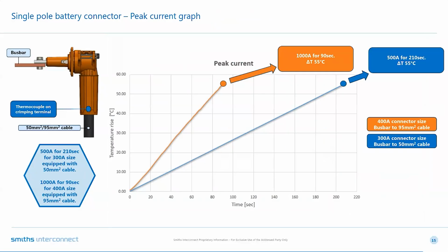The last test we are going to present is the peak current one that we mentioned before. The setup is the same as before, but providing the connector with a current value greater than the nominal one. This test simulates a typical operating situation when there is a demand for extra current just for a limited amount of time without exceeding in the connector overheating. Analyzing the chart, the x-axis shows the time in seconds, and the y-axis shows the temperature difference between the connector and the ambient. The test stops when the temperature difference exceeds 55 degrees.